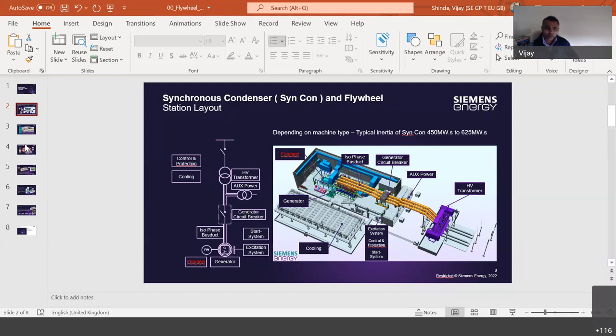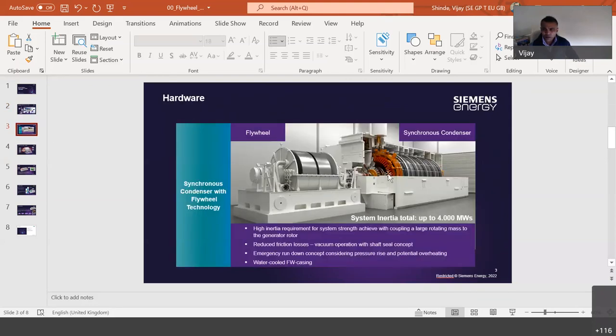If we are looking at a system which needs higher inertia, then we would want to include a flywheel on the same shaft of the generator. So this is the generator, which when I say generator, it means synchronous condenser. When we extend the shaft with the clutch, and this is a flywheel, which can offer inertia up to 4,000 megawatt seconds. That's quite a large inertia. Great Britain recently procured inertia of about 7.5 gigawatt seconds, and we're talking about 4,000 megawatt seconds here. So that's a kind of large inertia we're discussing here.